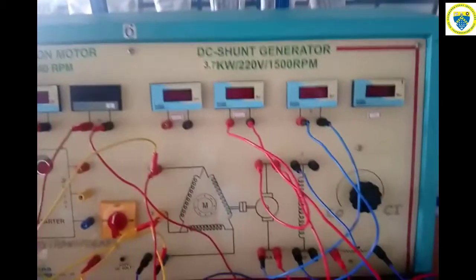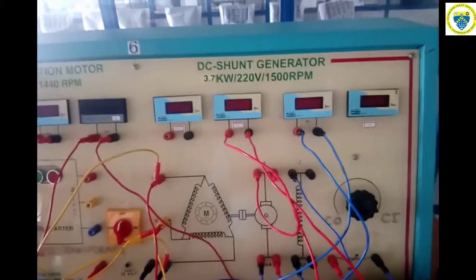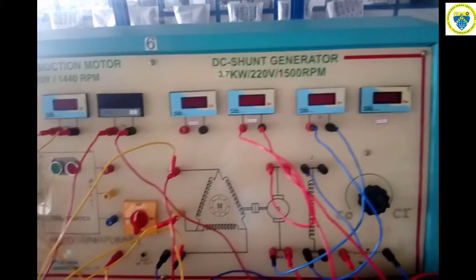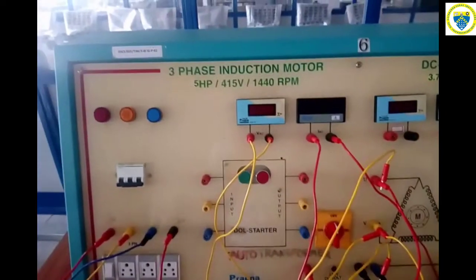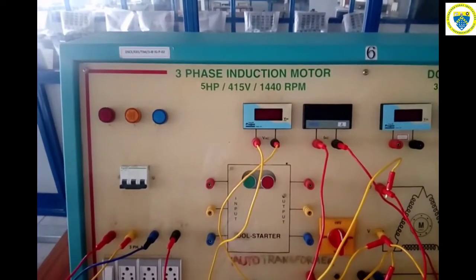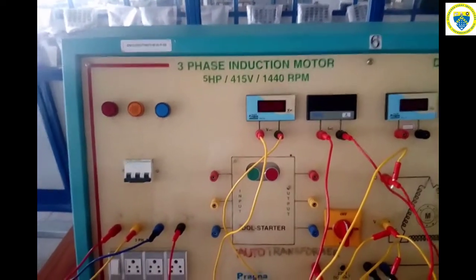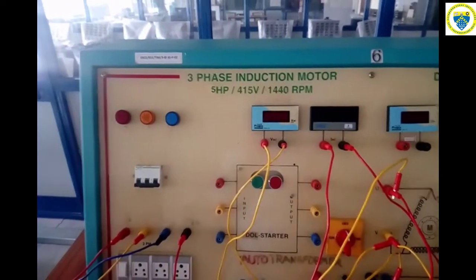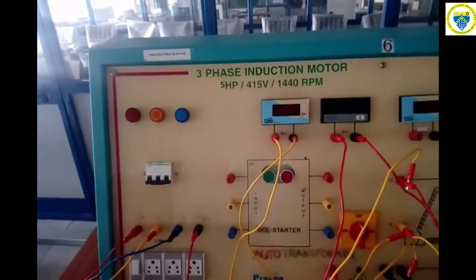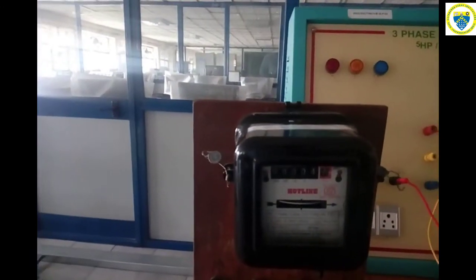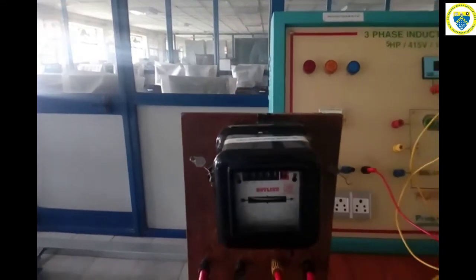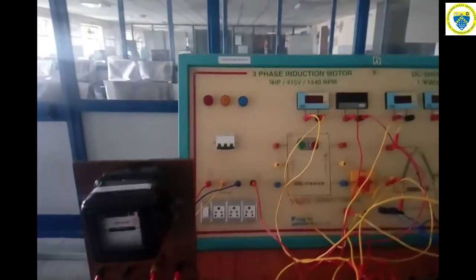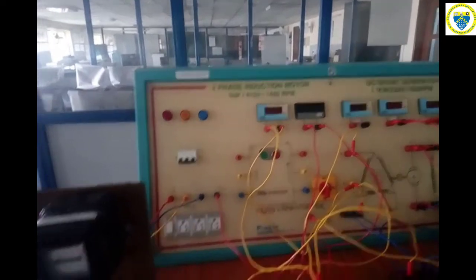It means the DC shunt generator is acting as a DC motor, and it is in turn driving the induction motor. That is, at that instant, the three-phase induction motor starts acting as an induction generator. So by observing the aluminum disc rotating in the opposite direction, it shows the energy is transferred from the induction generator to the supply.